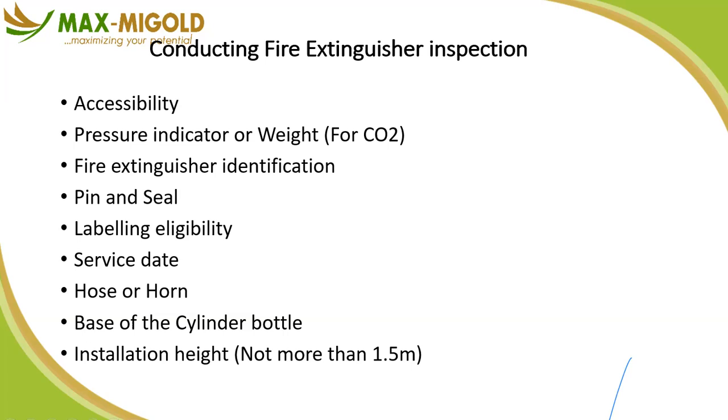On your database, you should also have this spelled out. Fire extinguisher identification and location. For us, we even say fire extinguisher identification, fire extinguisher type, fire extinguisher size, then location. Then you can even have a tracker calling out the first time it was bought and the time it was last serviced.